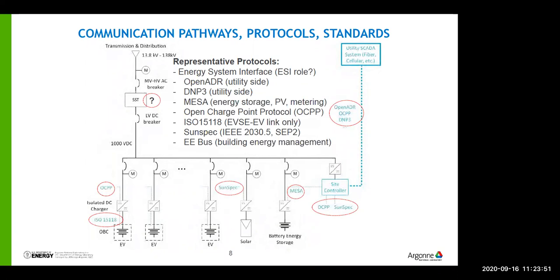That's where we're working on these high efficiency pathways that take the utility-owned distribution node, with all NEC and other DC-rated equipment. Just doing the simple math: if I have a 1,200 volt distribution line and a 20 kilowatt class 4 truck charger, that's 16 amps, so that's a 12 gauge wire. It's like, I get it—a 12 gauge wire feeding a shoebox charging my Amazon delivery truck.